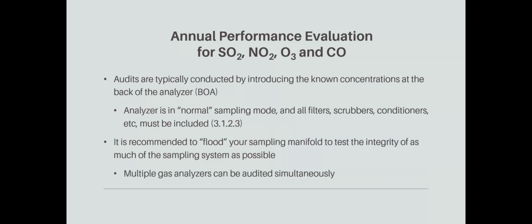It is recommended that you flood your sampling manifold to test integrity of as much of the sampling system as possible. And this will allow you to actually audit multiple gas analyzers simultaneously as well, which will save time.